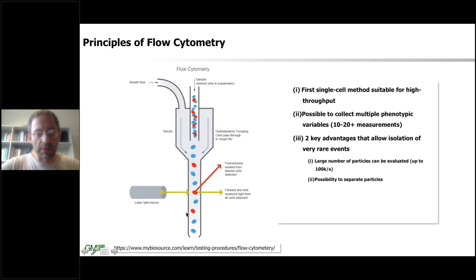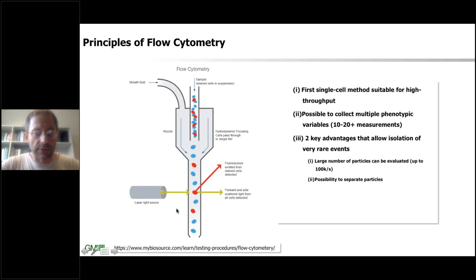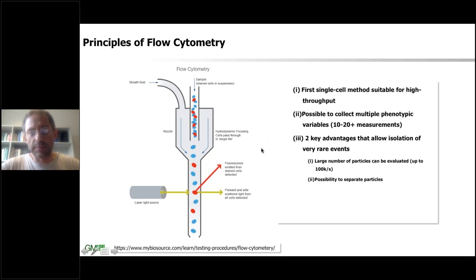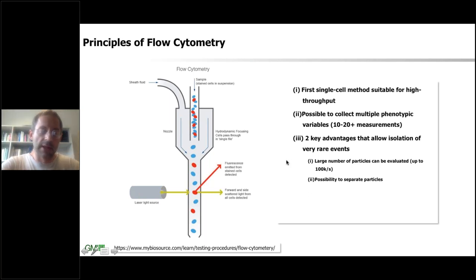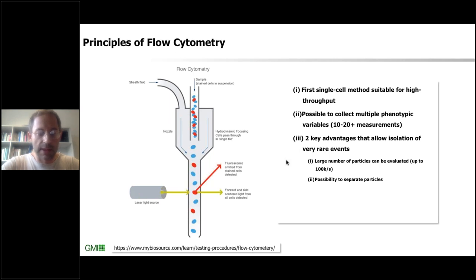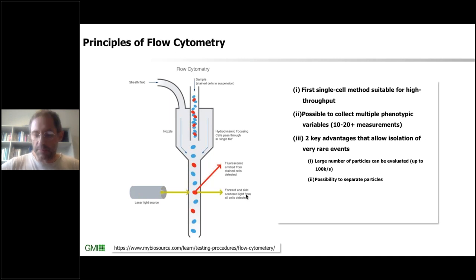That allows you to have single particles phenotyped by a laser light source. You can measure many different parameters — you can measure the scattering of your particle and also the fluorescent intensities. It's really the first single cell method suitable for high throughput. Modern flow cytometers can collect more than 20 different parameters, up to 100,000 particles per second, with the possibility to actually sort those particles. You can think of a flow cytometer as a high throughput phenotyping device for cellular and subcellular particles.